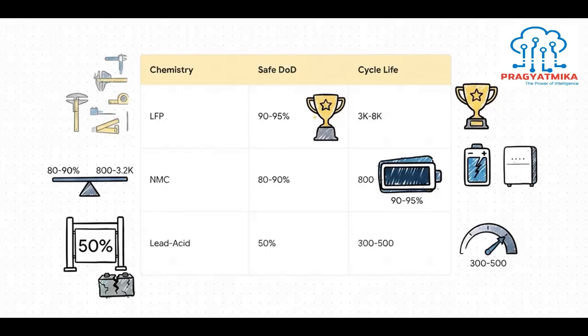If you're using a lead-acid battery, you are hard capped at a 50% depth of discharge. If you push past that, you're going to completely ruin its cycle life. Lithium iron phosphate, or LFP, on the other hand, is the gold standard for stationary storage precisely because it lets you safely use 90 to 95% of the battery's true stored energy.